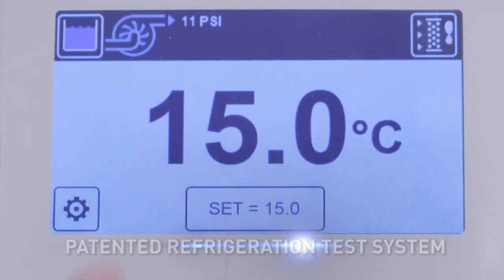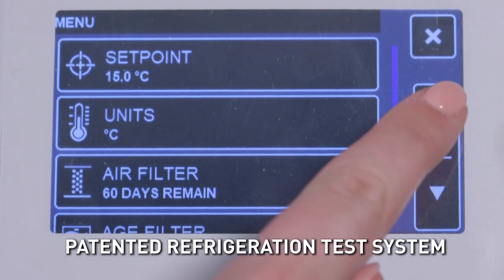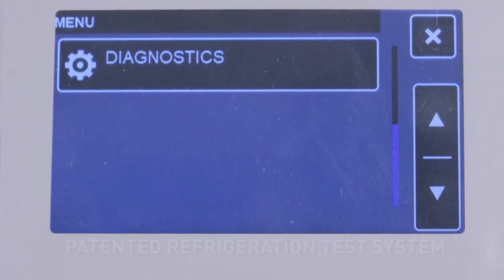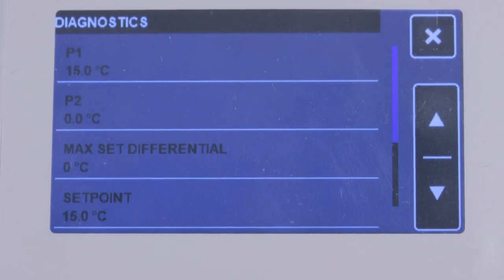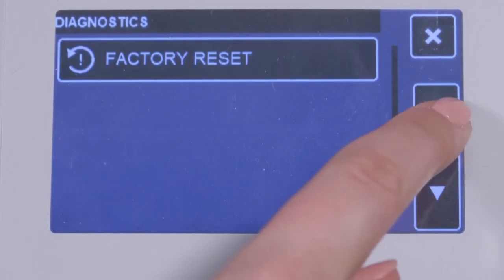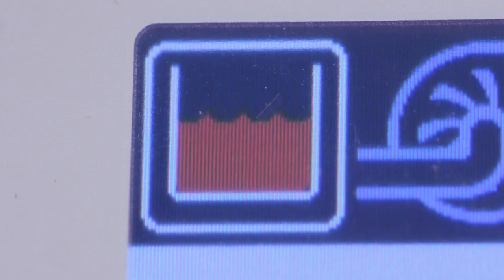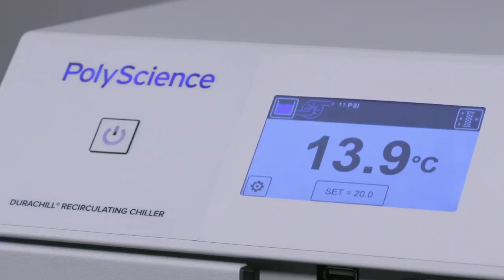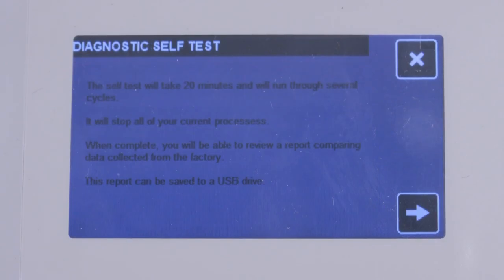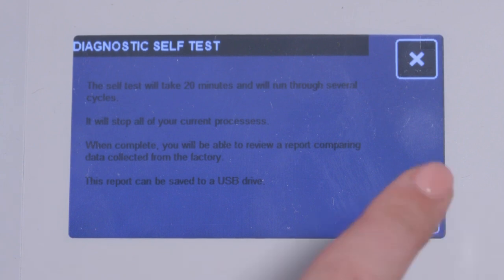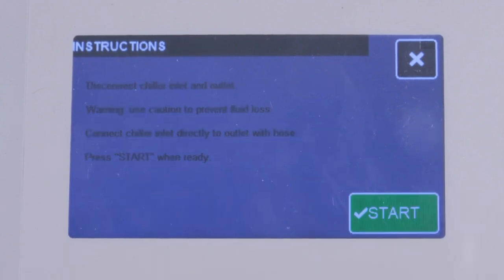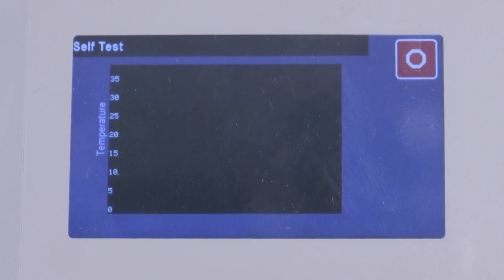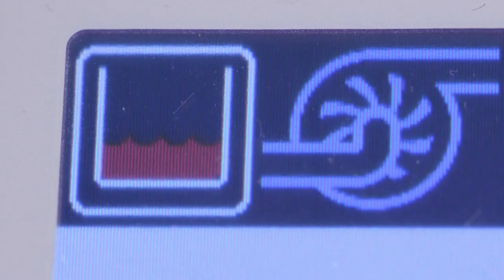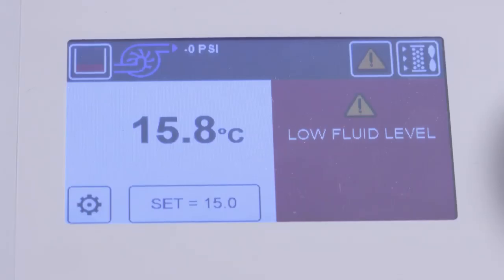Our innovative and patented refrigeration test system allows us to store all the parameters of each individual DuraChill chiller in its onboard memory on the day it was built. Simply put, at any point that you feel the chiller is not performing as expected, or you're not getting the temperature that you believe you should be getting, simply initiate the refrigeration test system and it will provide a comparative result of performance data from day 1 to current date. This gives you the ability to isolate the problem and quickly diagnose what needs to be done next.